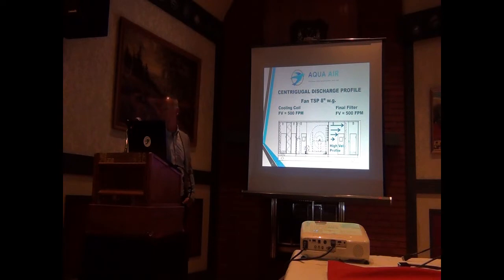When it gets to this fan, it's going to be throwing out the front discharge of this fan area here at 3,000, 3,500 or even higher feet per minute. Most of the volume will be at the top, and it tails off as it goes down towards the bottom of the fan. That's the fan profile. As you can see, these filters in front, if these are the final filters and you had most of your velocity and air volume going to the top, what do you think is going to happen? Those top filters are going to load up a lot faster than the bottom filters.